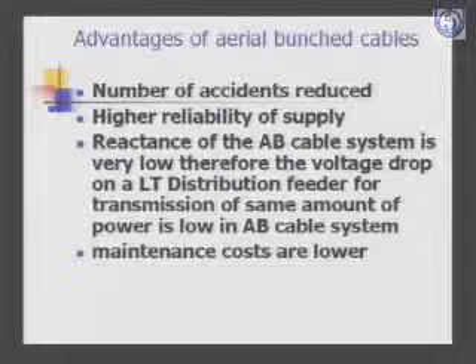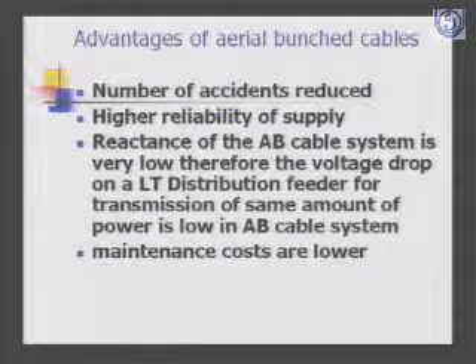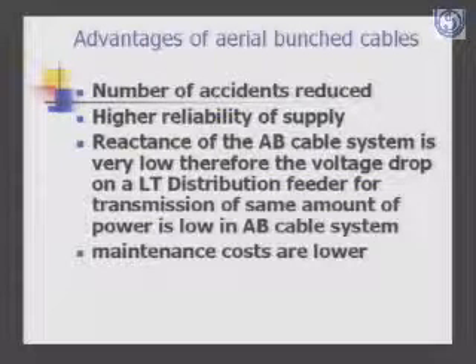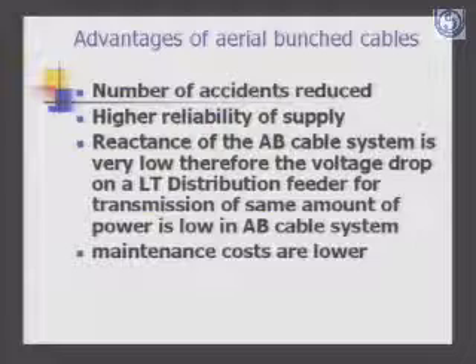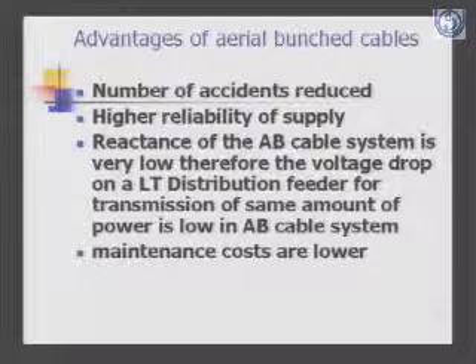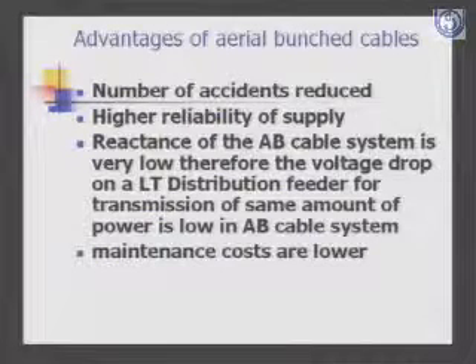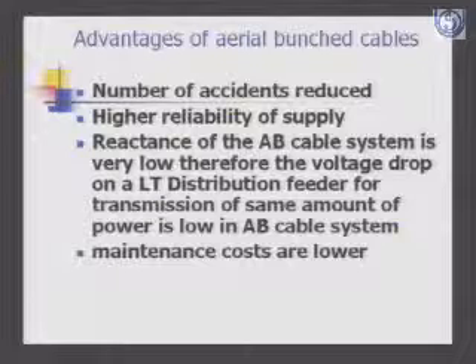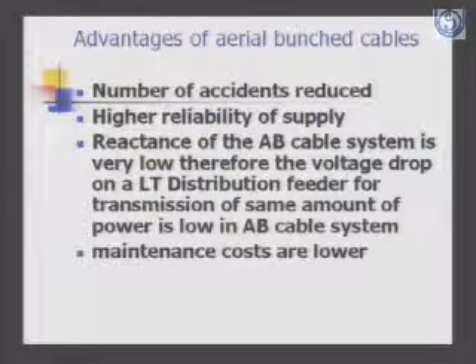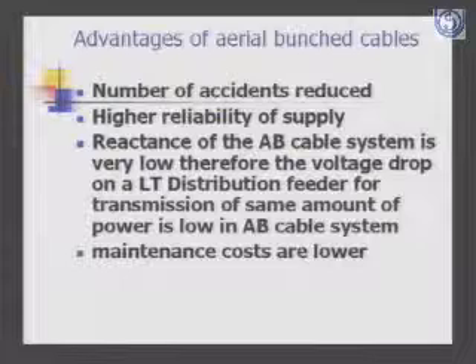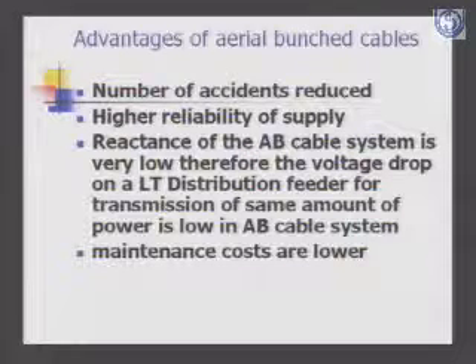The number of accidents is reduced because there is no bare overhead line. Higher reliability of supply is there as faults are reduced. The reactance of the AB cable system is very low, therefore the voltage drop on an LT distribution feeder for transmission of the same amount of power is low in the AB cable system, and maintenance costs are lower. So you have many advantages of using the aerial bunched cable system, and they should especially be used in theft-prone areas.